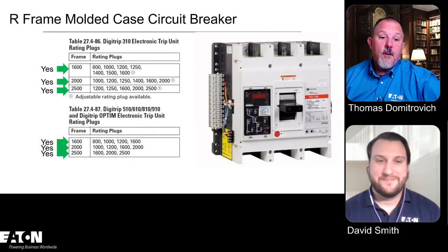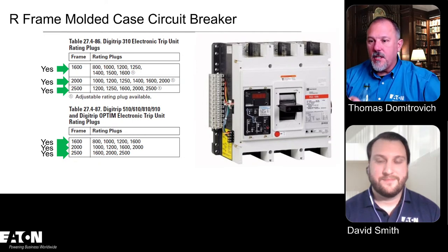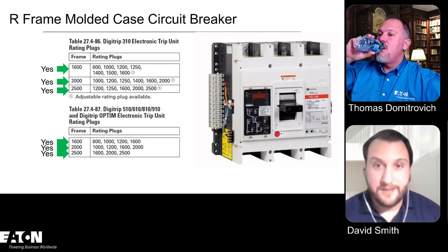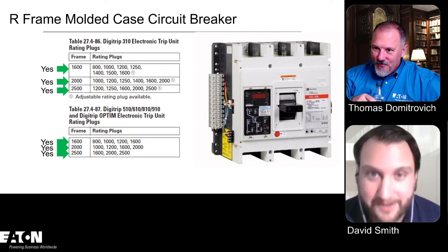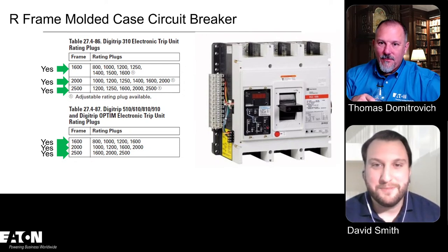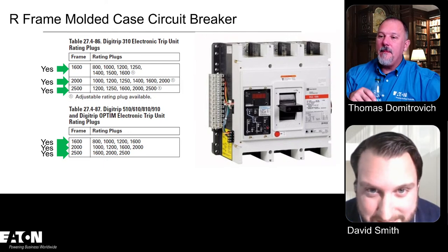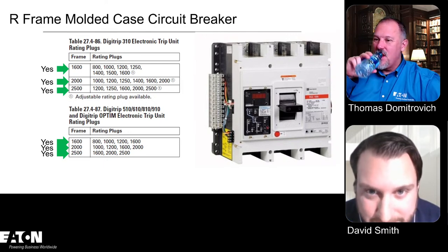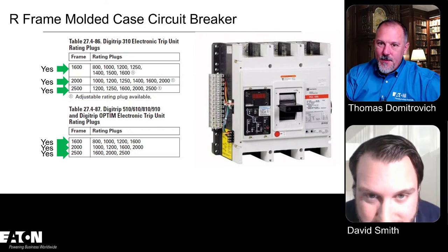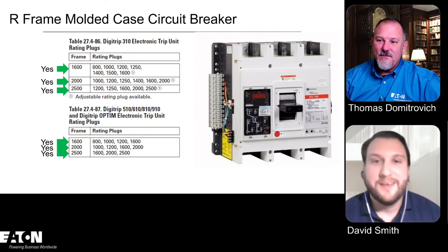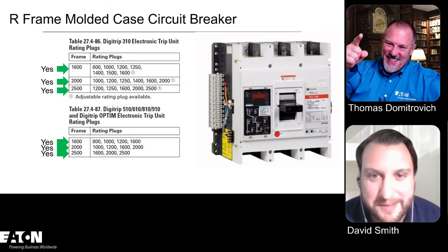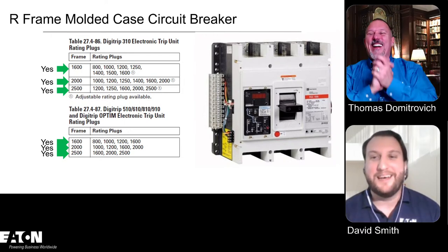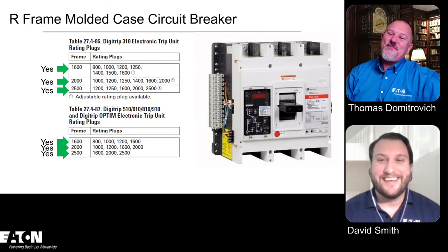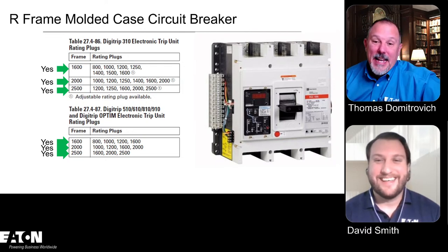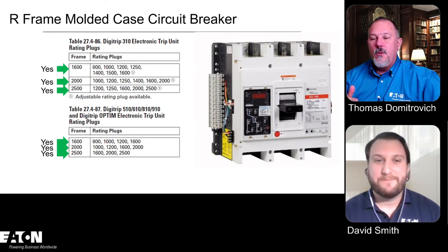Now these are the R-frame breakers. Which ones of these would you not have to have an arc reduction technology on, Mr. Smith? I would go with the 800 rated, the first one up there, the 16. What's the frame? 1600. 1600 frame. Because the frame is over 1200 amps on all of those, you would have to have it. Perfect, exactly right. So those can be adjusted to greater than 1200 amps.